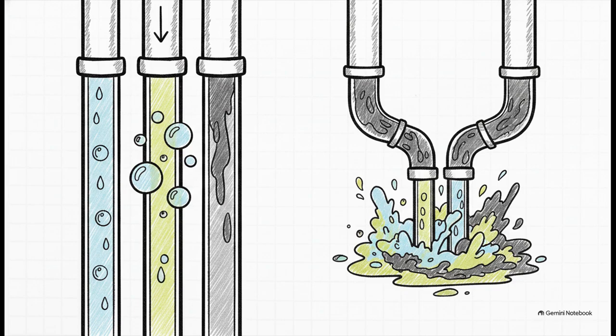You've probably heard of zero trust in cybersecurity. Well, it applies perfectly to industrial plumbing too. You have to establish totally separate collection paths for things like cooling tower discharge, chemical cleaning solutions, and potentially contaminated stormwater. Why? Because if you mix clean condensate with high salinity reject water, that clean water inherits the same toxic disposal problem as the heavy brine.